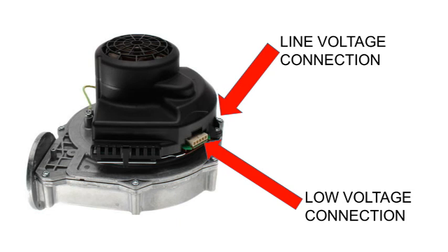The display is powered from the low voltage side, but the blower is also taking orders from the low voltage side. There is a low voltage and line voltage plug going to the blower. So, when we lose low voltage, the blower ramps right up to 100% and the screen, you guessed it, goes blank. Now, we will examine which components to check out to determine where and why our low voltage has gone missing. So, let's start with just the basic overview of where that low voltage comes from.